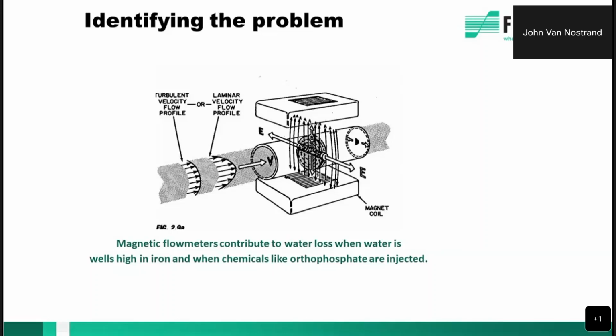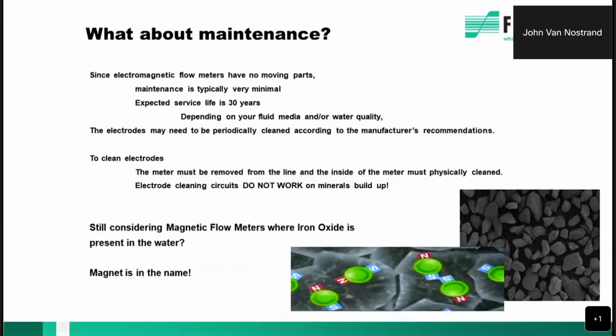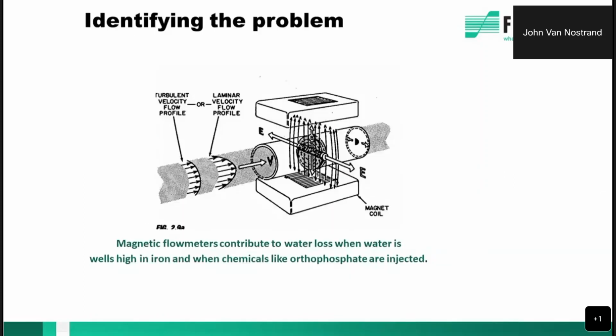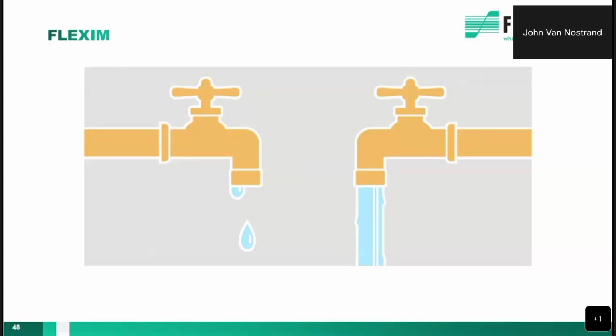But as the name implies, magnetic flow meter, you're creating a magnetic field and then sending a magnetic material through it. It sticks to it like glue. And again, that material builds up and it creates a bridge from one electrode to the other, creating a direct short. So over time, it'll read properly and then read lower and lower and lower. So that is a real issue.